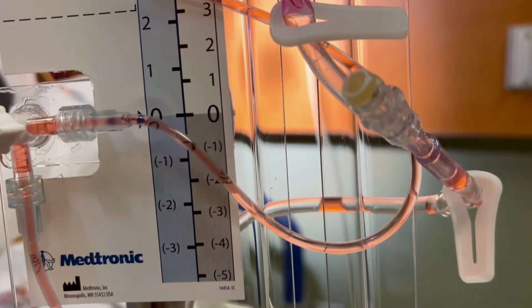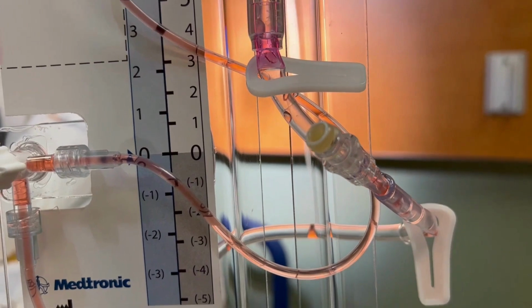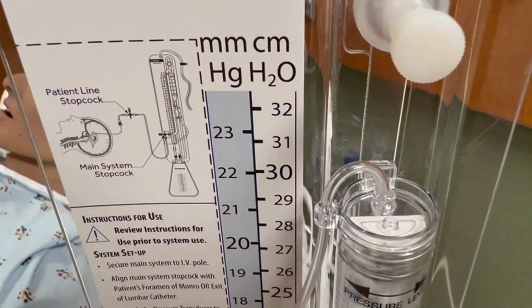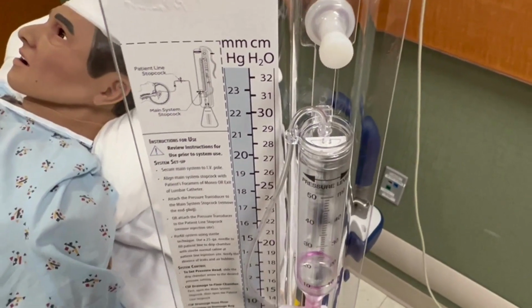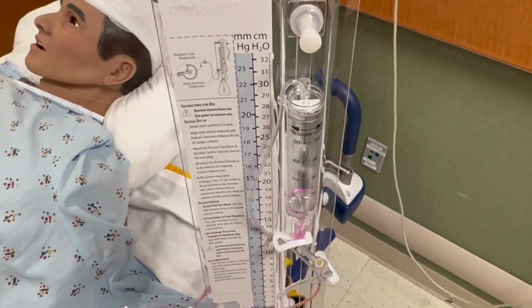To drain the CSF fluid that has accumulated in the drip chamber, open the 2 slide clamps so that the fluid will drain into the collection bag that is below. Do not squeeze the drip chamber because that could cause it to break or crack. If this happens, the entire system will need to be replaced.